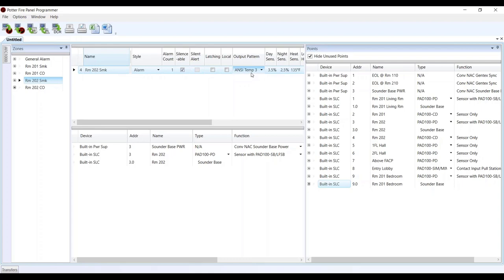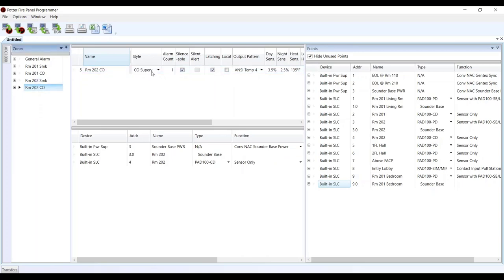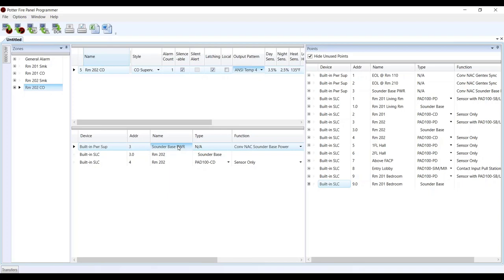The other question is about separate sound for CO — we are doing that based on our zone settings. The output pattern determines the sounder base pattern: temporal 3 for smoke detector alarm in the room, temporal 4 for CO. Also, make sure you have the right sounder base power in there. If you had rooms on the first floor with one circuit and a separate circuit for the second floor, you've got to make sure you're putting the right power in that zone — whatever power circuit is running to that particular sounder base.